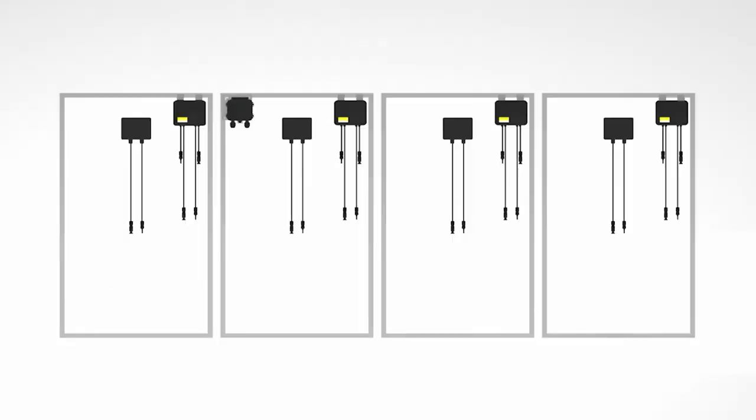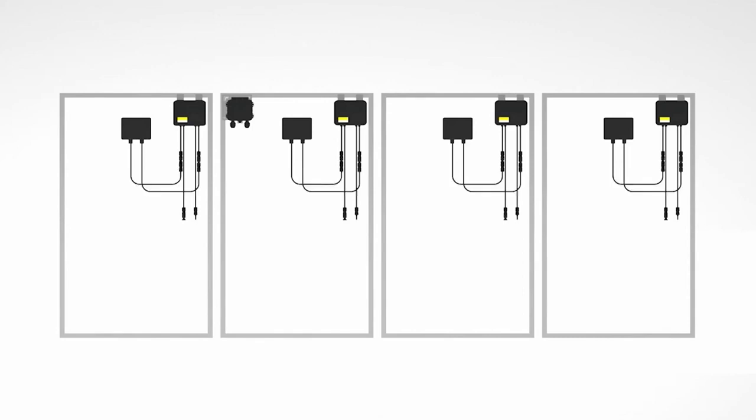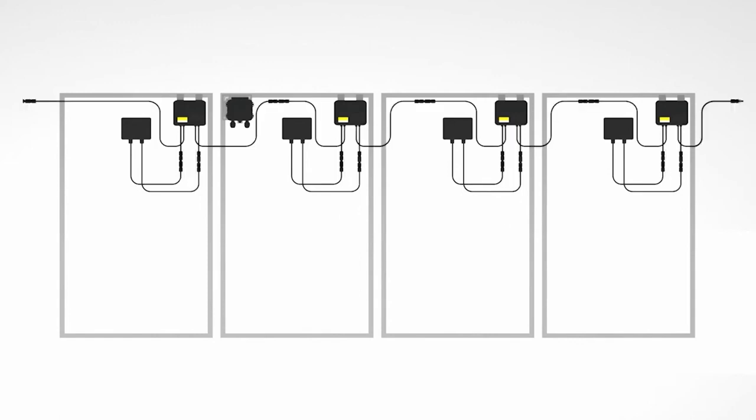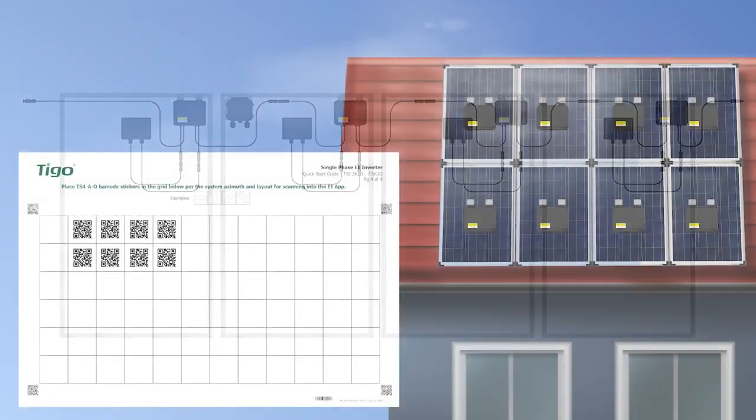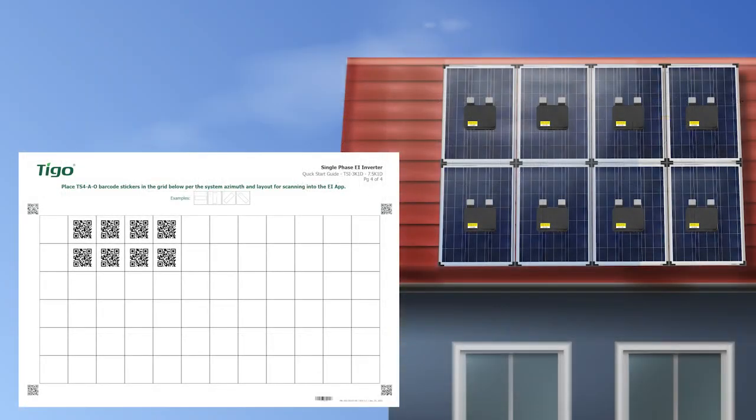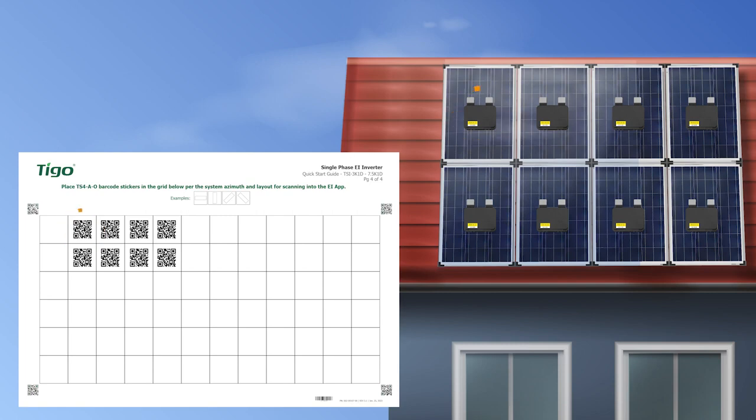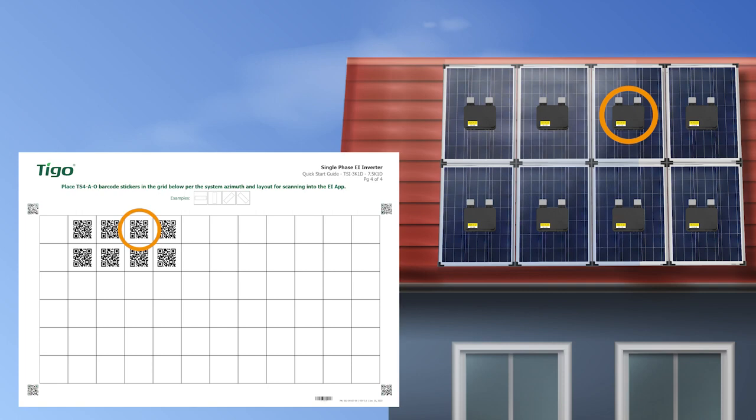For wiring, first connect the short wires from the TS4 to the module. Then we connect the longer wires from the TS4 to the neighboring TS4 to form a chain. The positive and negative wires remaining at both ends of the PV string will be connected directly to the inverter. It is very important to remove the serial number label from each of our optimizers and place them on the physical layout template in the same position as the TS4 are installed on top of your roof for future reference.